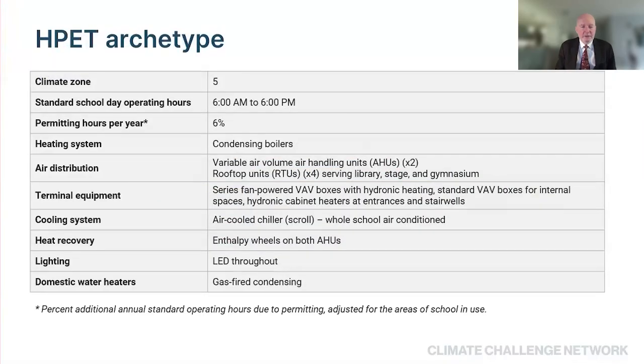Forgive the acronym, but I got tired writing out high performance energy target, so the HPET is here to stay. This is the archetype equipment. They do have exhaust air heat recovery as their standard. The school with the highest gas use had an enthalpy wheel failure, and because it's incorporated in the air handling unit, it can't be repaired, so they have to wait until end of life. But it's LED lighting, gas-fired condensing boilers — exactly what the large majority of new schools we found are running.